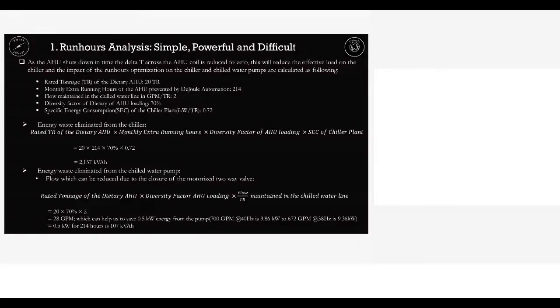So energy waste eliminated from the chiller. This is the formula: rated TR of the AHU, monthly extra running hours prevented, diversity factor of loading, into specific energy consumption of the plant. As I have told, for 20 TR equipment, that is 214 hours and 70% loading and 0.72, it is actually from the chiller. So from the chiller, this much consumption we are able to save because this particular equipment, the air handling unit, was shut down in time.